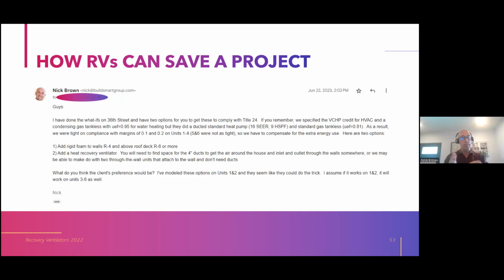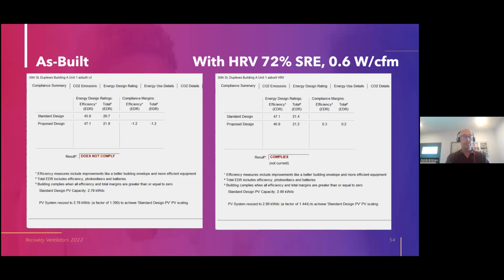And I talked to them about what that meant. You need to find space for the ducts. You need to find space for the unit. They also make through the wall units, which I'll show you in a minute. So they said, okay, we'd prefer the HRV. And here's the before and after. Before, we were 1.2 efficiency EDR points away from compliance, as shown on the left. After, we were 0.3 better.